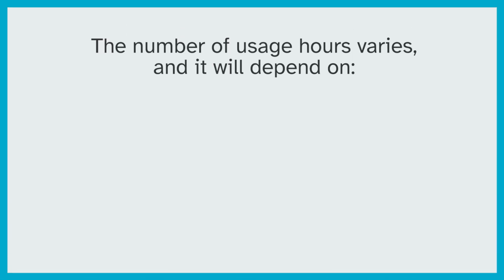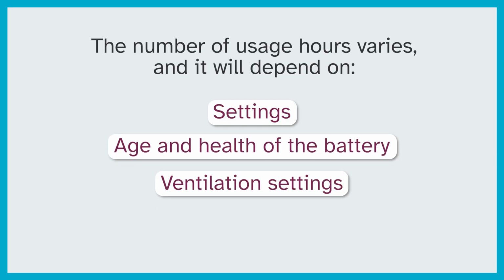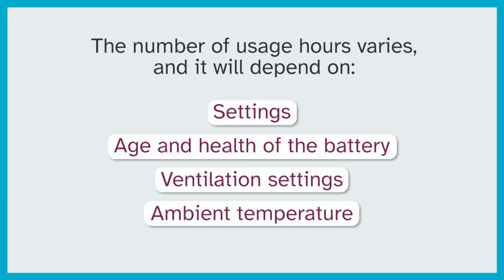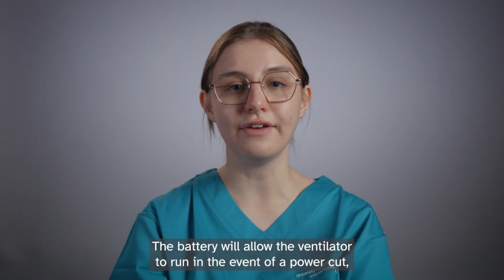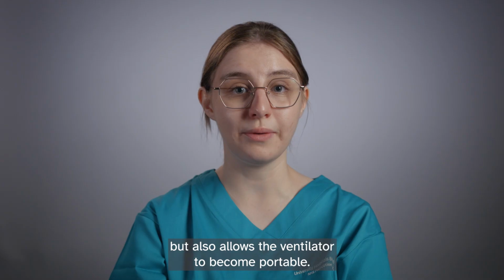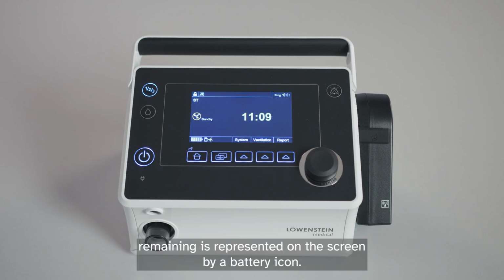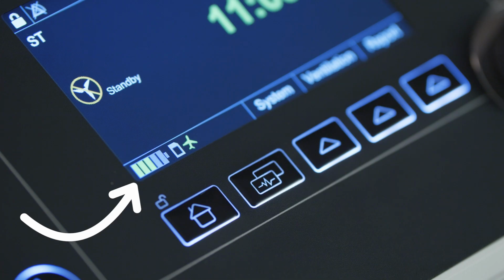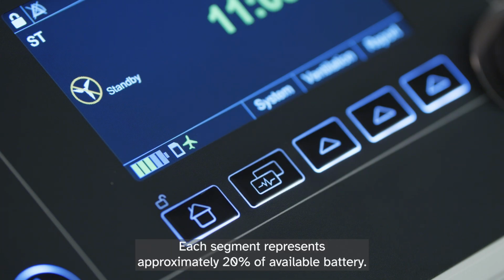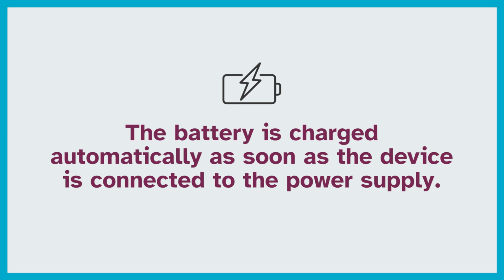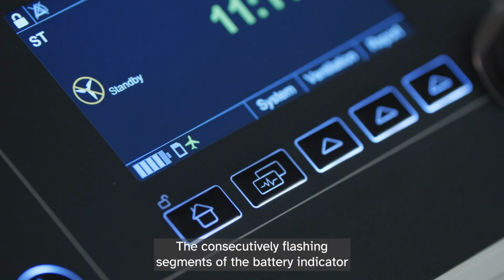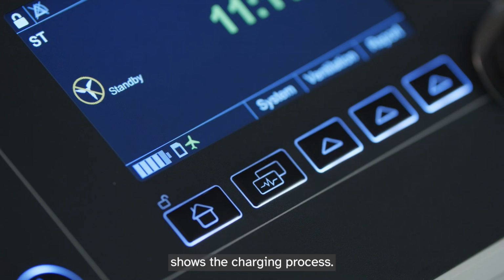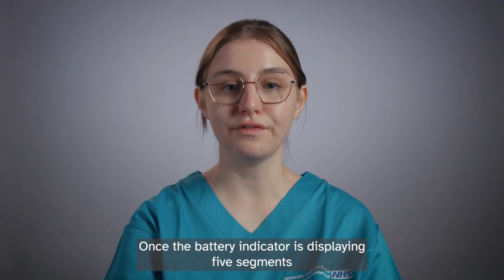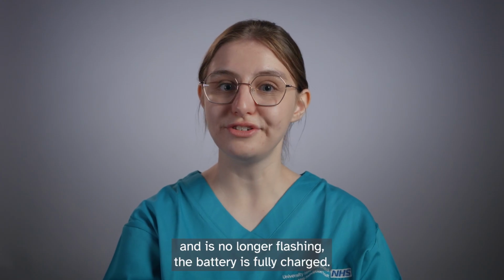The number of usage hours varies and will depend on your settings, the age and health of the battery, the ventilation settings, as well as ambient temperature. The battery will allow the ventilator to run in the event of a power cut, but also allows the ventilator to become portable. The amount of battery power remaining is represented on the screen by a battery icon. Each segment represents approximately 20% of available battery. The battery is charged automatically as soon as the device is connected to the power supply. The consecutively flashing segments of the battery indicator show the charging process. Once the battery indicator is displaying 5 segments and is no longer flashing, the battery is fully charged.